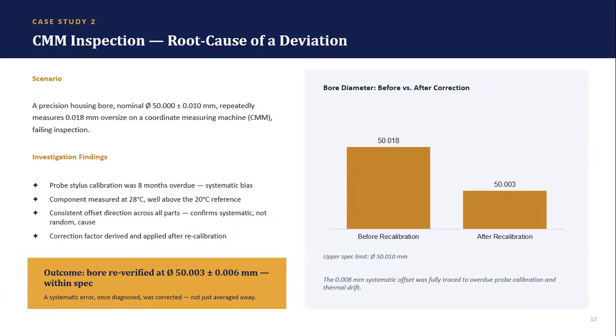After recalibration and application of the appropriate correction, the bore was re-verified at 50.003 millimeter plus or minus 0.006 millimeter. This case study demonstrates a very important engineering principle. A systematic error should not simply be averaged away. It must be identified, investigated, and corrected.